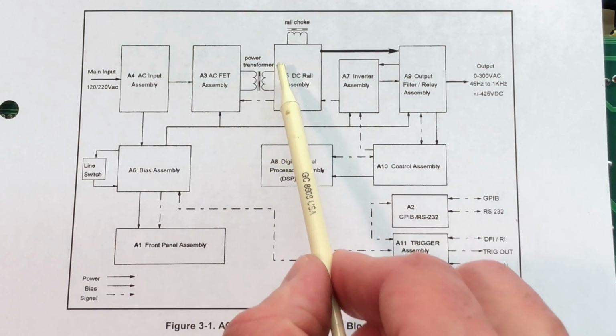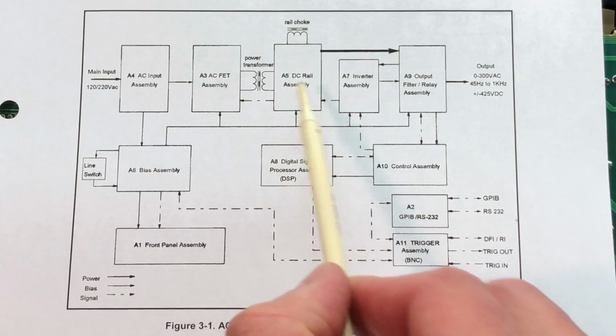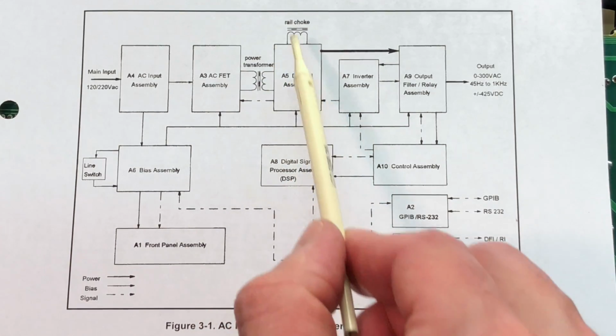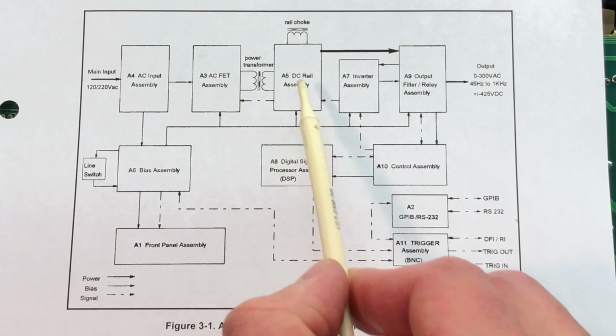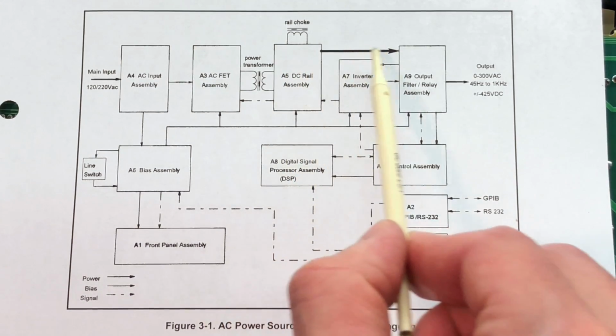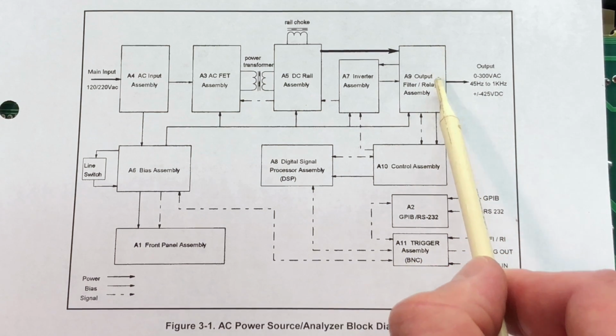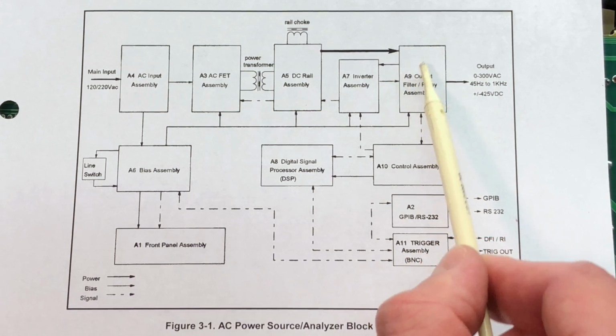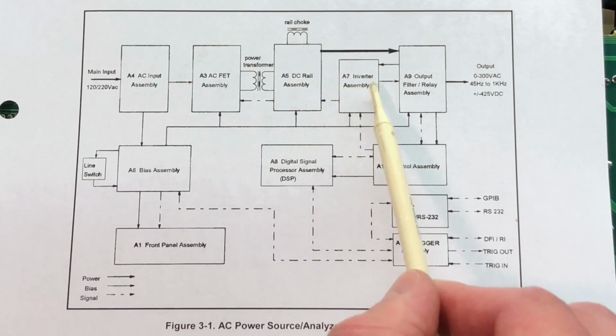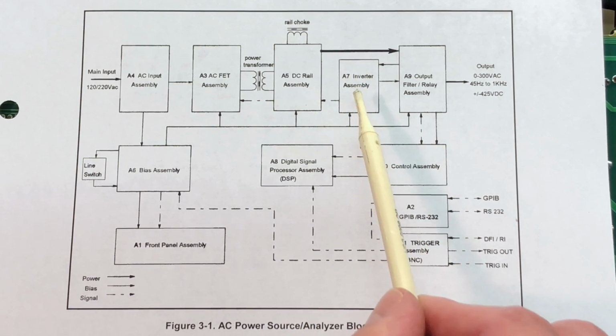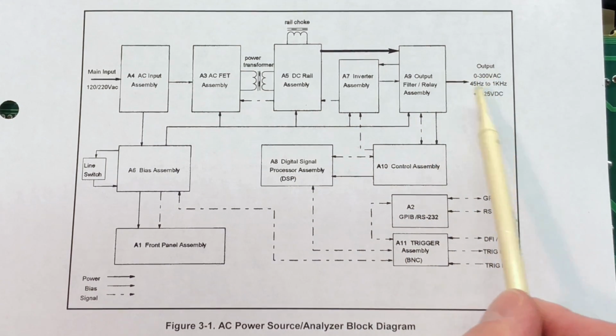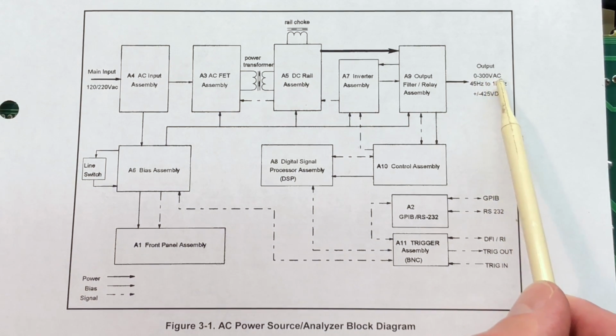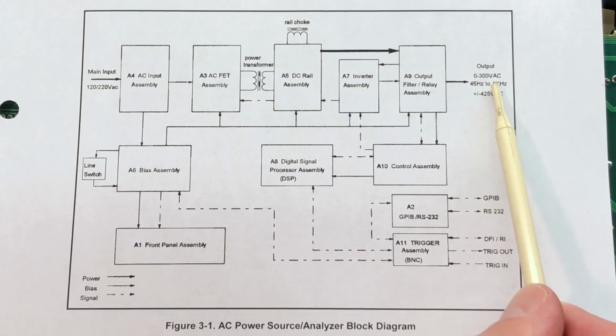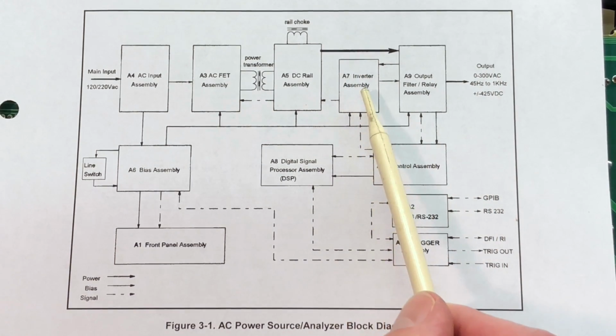The output of this transformer is of course a high frequency AC signal, and it's coming into the DC rail assembly. You can see there's a rail choke, some filtering going on there. The DC rail assembly creates a very high voltage DC, which comes over here to the output, filter, and relay assembly. But that high voltage DC is actually returned back over here to the inverter assembly. This inverter assembly is really key because it creates the various voltages and frequencies that this AC power source is capable of. You can see the output can be 0 to 300 volts AC, and it can vary from 45 hertz to 1 kilohertz. All of that voltage and frequency control is happening because of this inverter assembly.